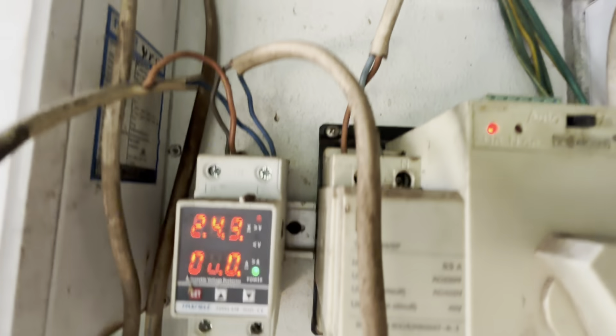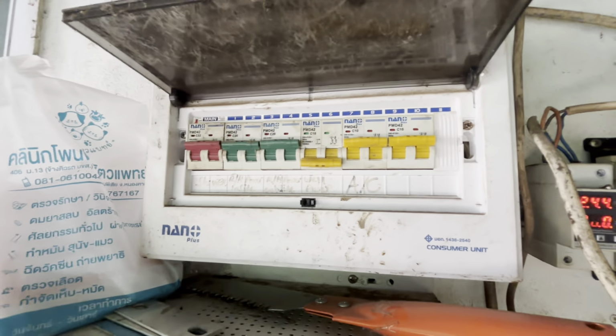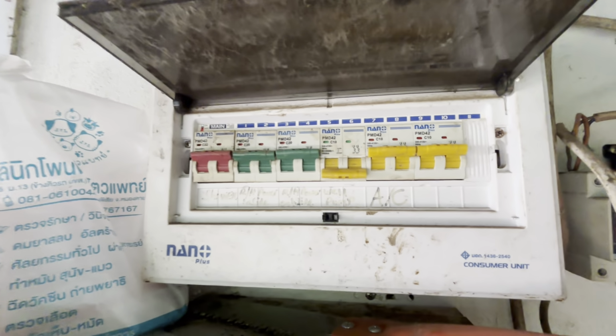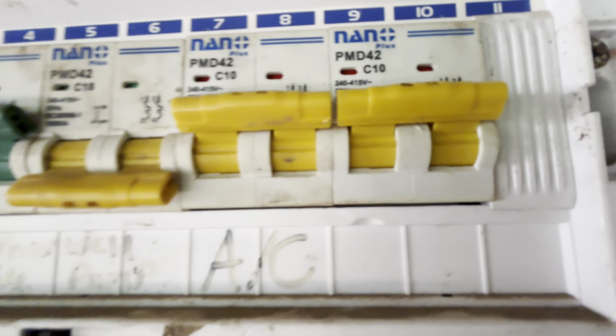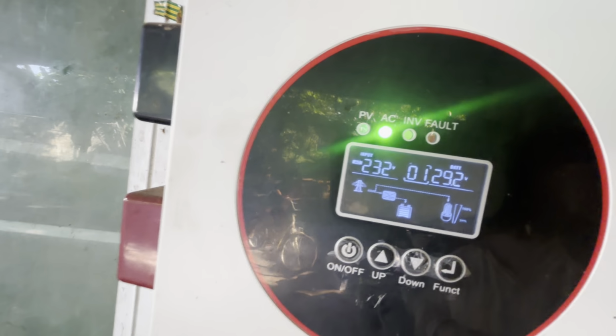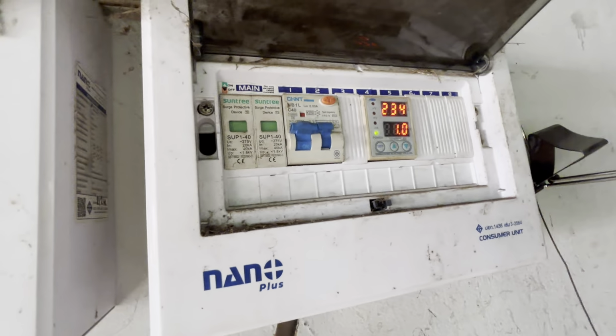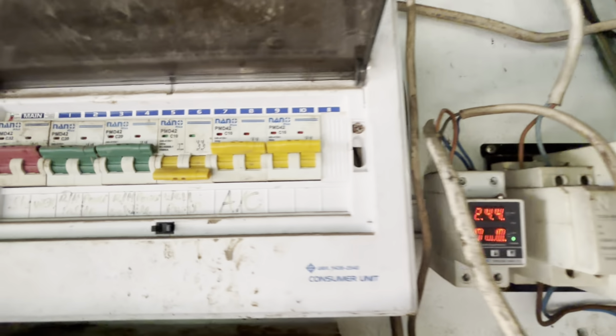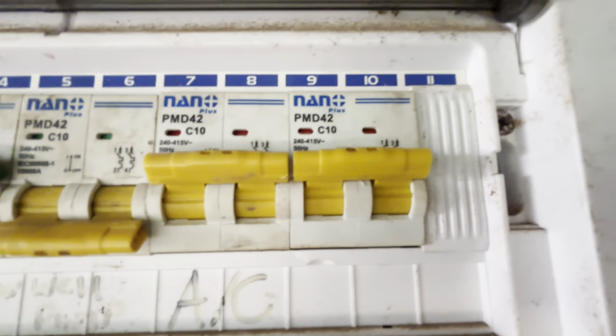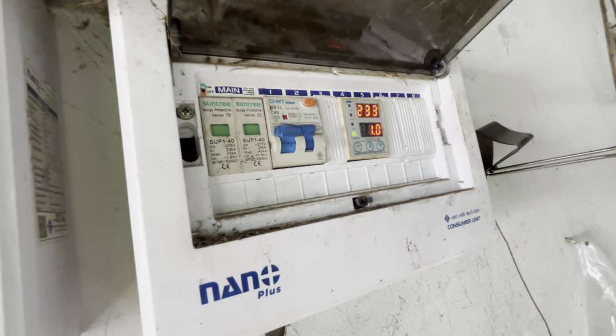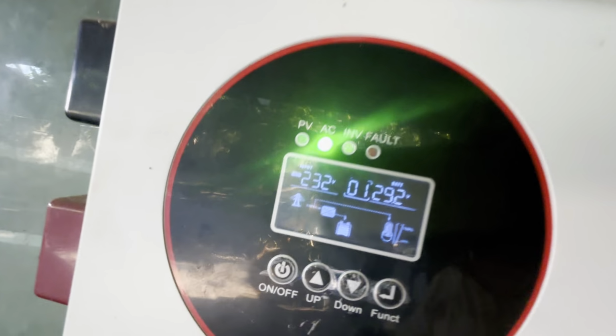So what would also happen, by the fact that it's switched over and there's no power there, would also be no power in the non-essential. But this is the non-essential side. So that breaker there puts 240 volts to here, which we're sort of seeing here, right? Now, this breaker would be on, but because that power has gone, this board would be dead, so there'd be no power here.